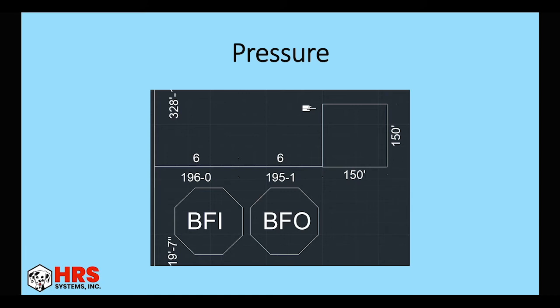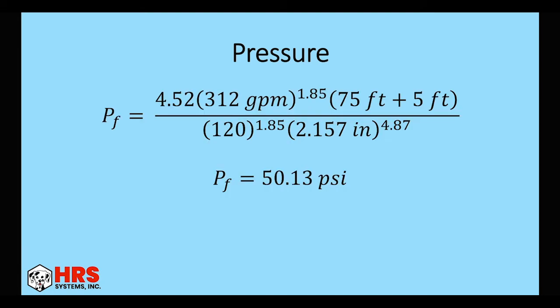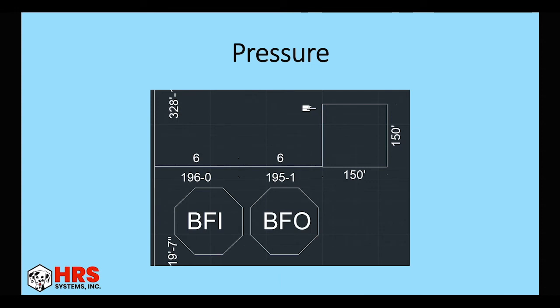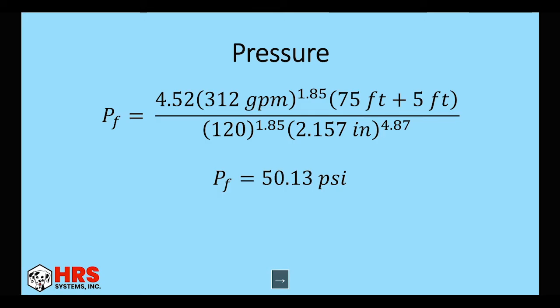And this is our basic floor plan layout. So the building's 150 by 150. So we'll take the 312 GPM. We'll say it's 75 feet for the branch line. So I took the middle of the building and just went to the cross main on one side. Plus 5 feet for the fittings. Our C-factor is 120. Our internal diameter, 2.157. This gives us a pressure loss of 50.13. So you can see here, this is the absolute worst case scenario. It's all of the design area flowing through one branch line. And it's flowing halfway through the branch line. So again, this is worst possible case scenario.